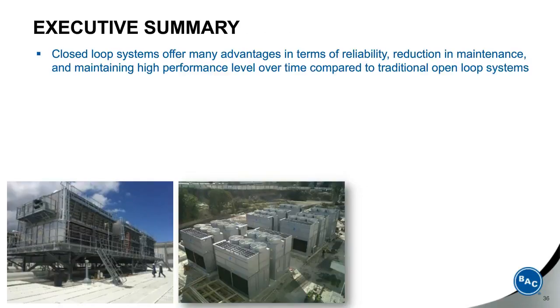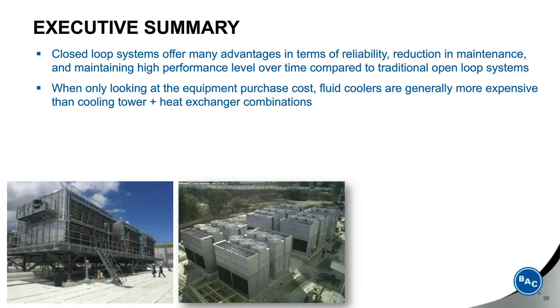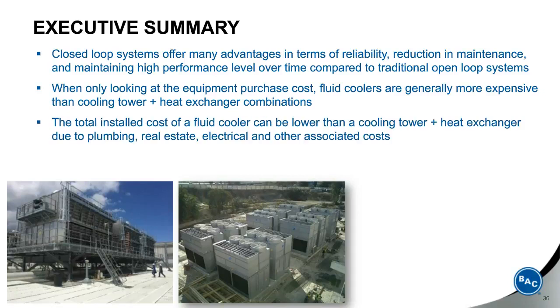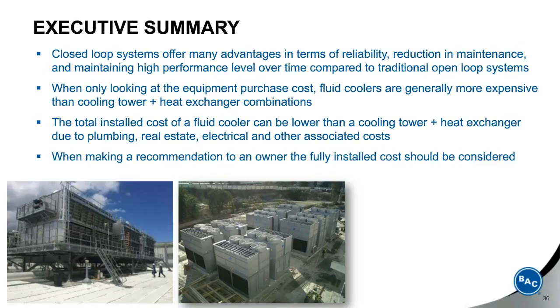Closed-loop systems offer many advantages in terms of reliability, reduction in maintenance, and maintaining high performance levels over time compared to traditional open-loop systems. When only looking at the equipment purchase cost, fluid coolers are generally more expensive than the cooling tower and heat exchanger combinations. The total install cost of a fluid cooler can be lower than a cooling tower and heat exchanger due to the costs associated with plumbing, real estate, electrical, and other costs that we spoke about earlier. So when making a recommendation to an owner, the fully installed cost should be considered.